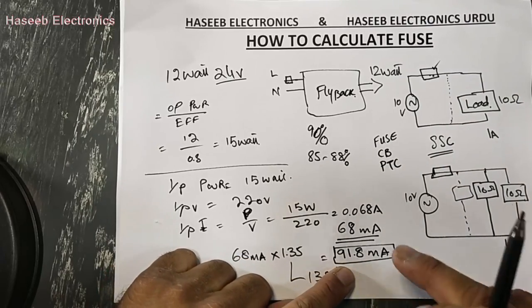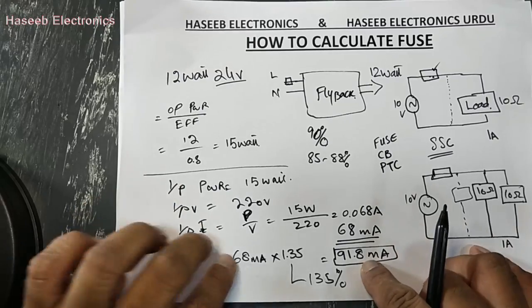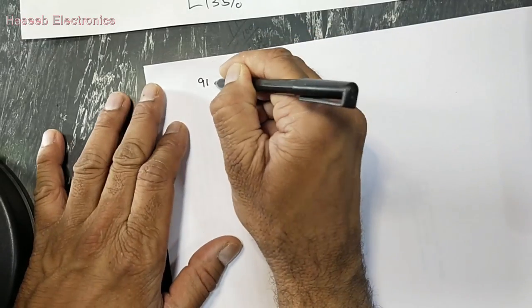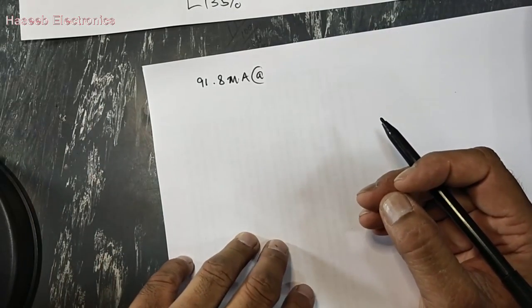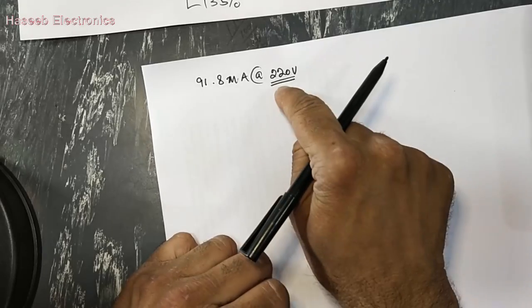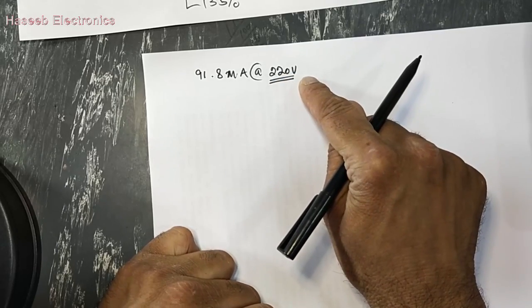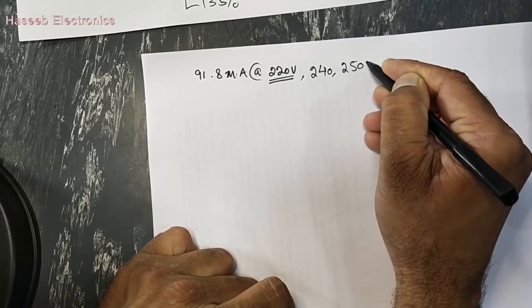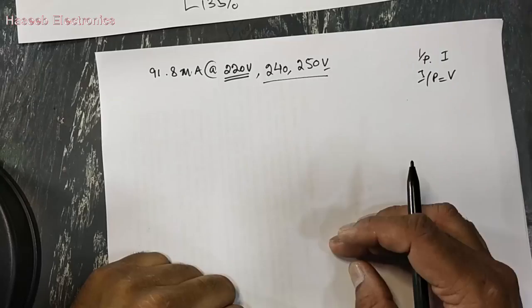Now we need to select the next standard value above 91.8 milliampere — we can say 100 milliampere or 125 milliampere. For the voltage value: that is 220 volt, and the voltage of the fuse must be equal to or above the operating voltage. You can select a fuse rated 220 volt, 240 volt, or 250 volt. So we now have covered two steps: input current and input voltage.